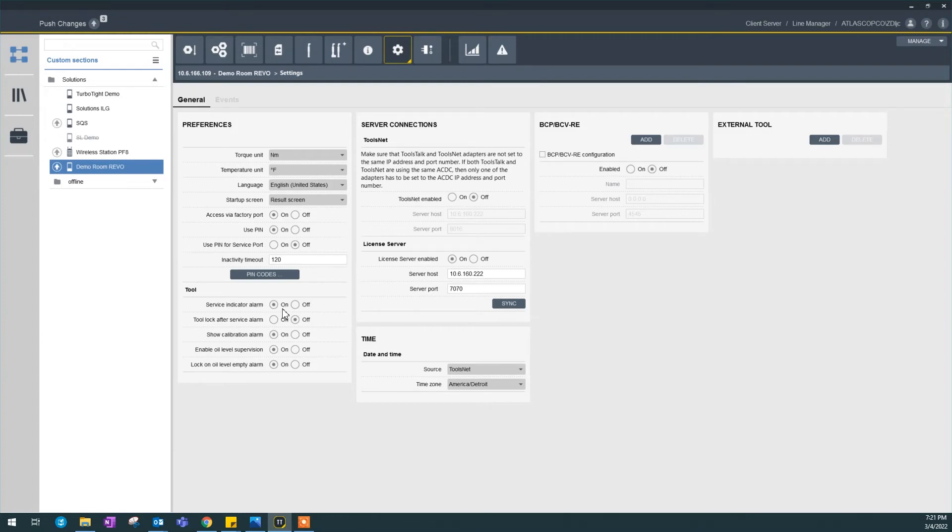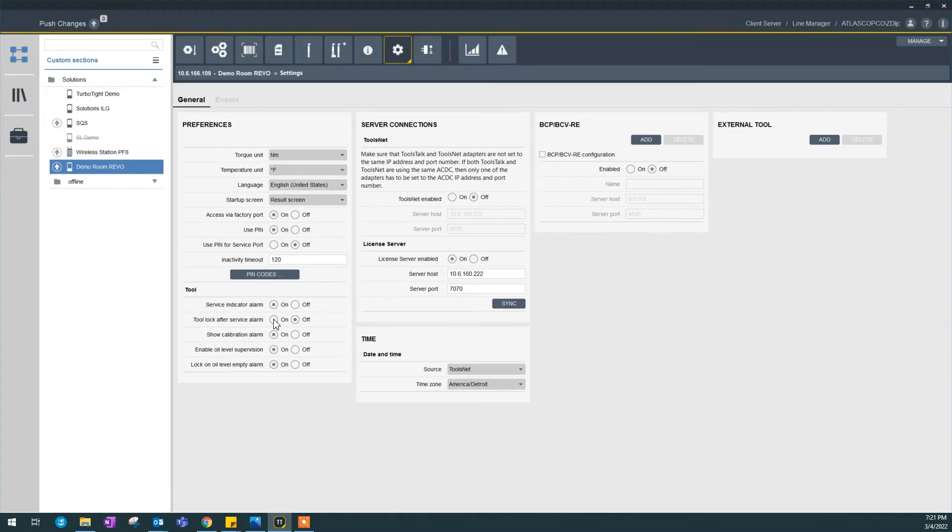When service interval is reached, tool lock after service alarm means if you turn this on and it requires calibration or the interval is reached, your tool will be locked to make sure you don't use a bad tool in the production line. That will be a little bit dangerous too because it will stop your production. Show calibration alarm. That's straightforward.